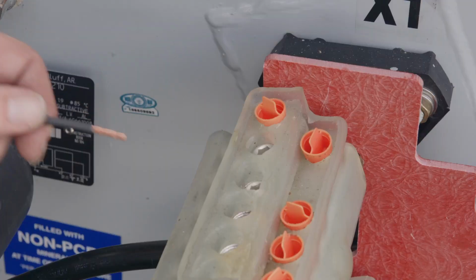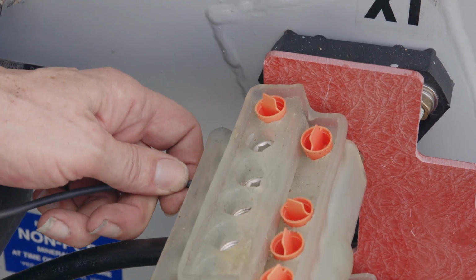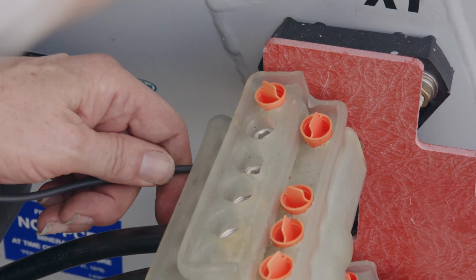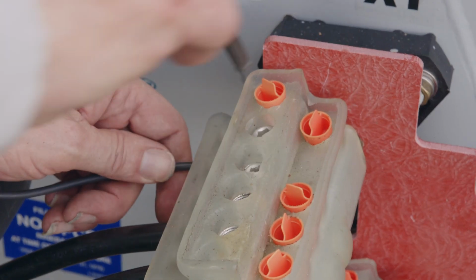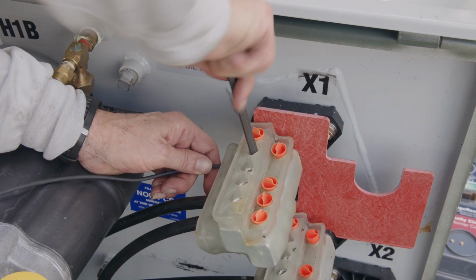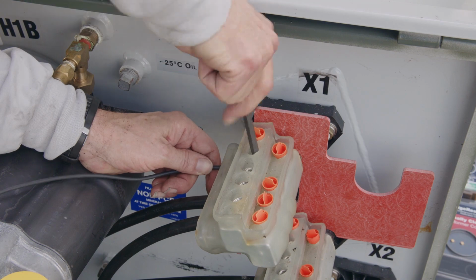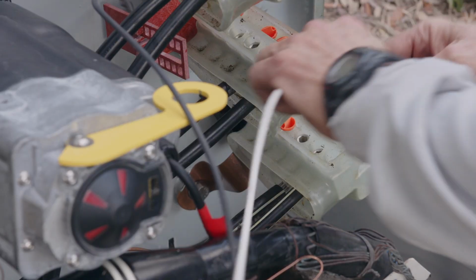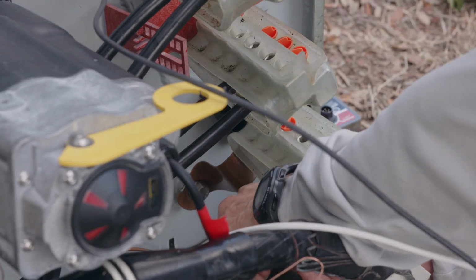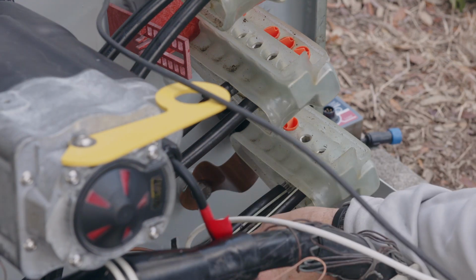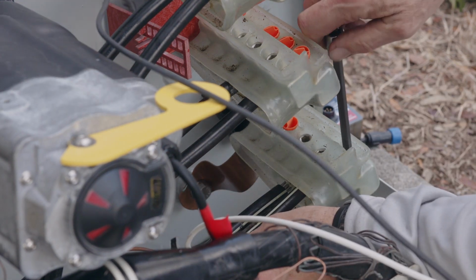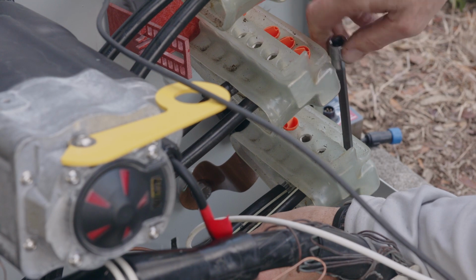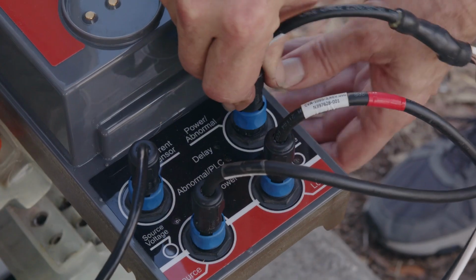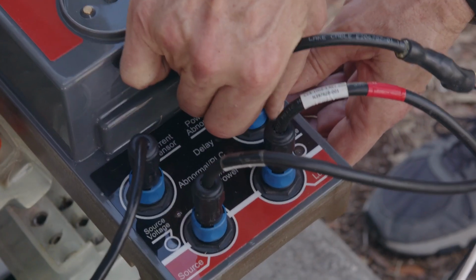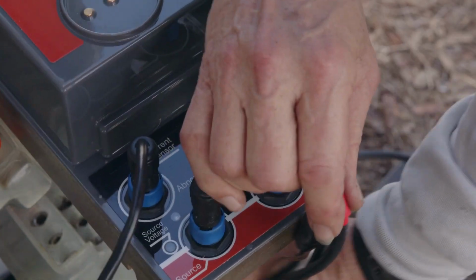A control power connector is included in the installation kit. Connect the black 10-gauge wire to X1 or X3 on the secondary transformer, and the white 10-gauge wire to X2. Typically, there is a lighting connection on the transformer's secondary connections that can be used for this purpose. Then, plug the 6-pin connector into the power abnormal connector on the control.